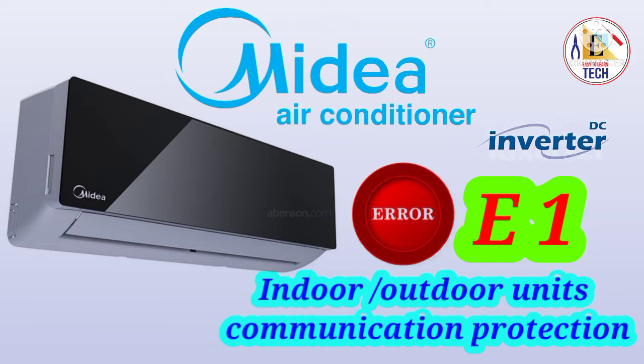If the continuity is good in your cable, then you have to check the output supply of your indoor PCB, if the indoor PCB output supply for the communication is good or not. If it is not good, then you have to change the indoor PCB. If the communication voltage for your outdoor PCB is not coming properly, it means your outdoor PCB is faulty. Need to change the outdoor PCB and your unit will be in working condition.